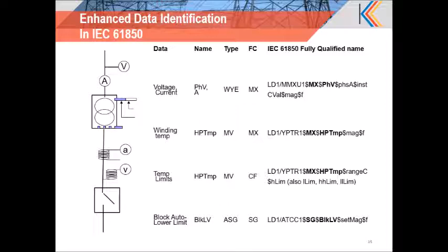So earlier we had direct CT-PT wirings and other wirings needed for the circuit breaker connected to the bay level equipment, and other communication can be through separate protocols like 103, DNP3 and all others, SPA, Courier, vendor protocols can be used. But here you can see the CTVTs and intelligent circuit breaker are connected to the merging unit, and this can exchange the data with different protection and control equipment in the bay level device using the station bus.